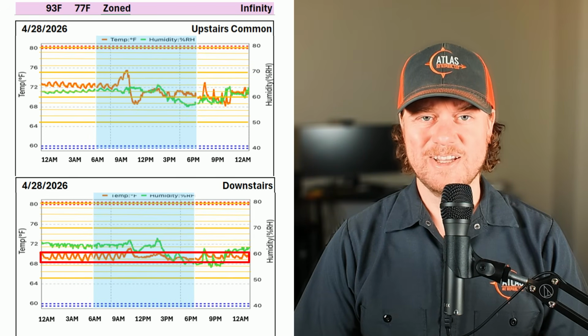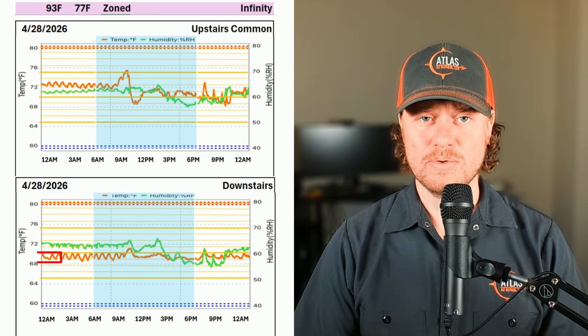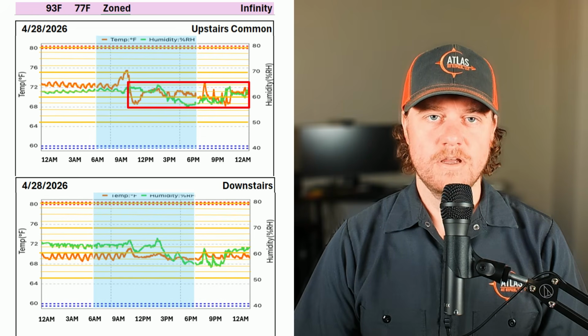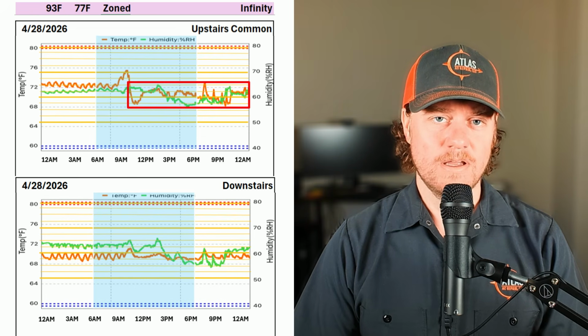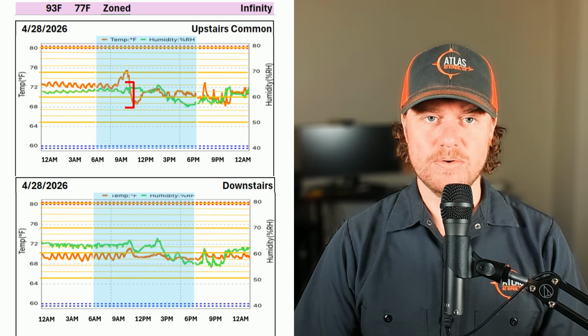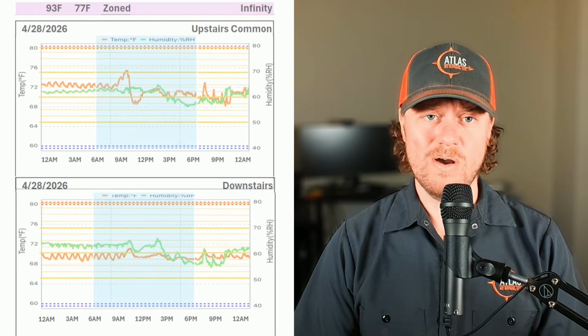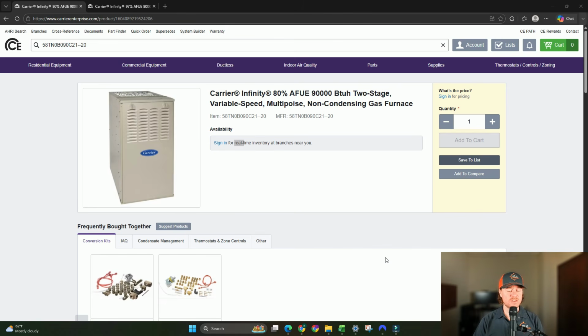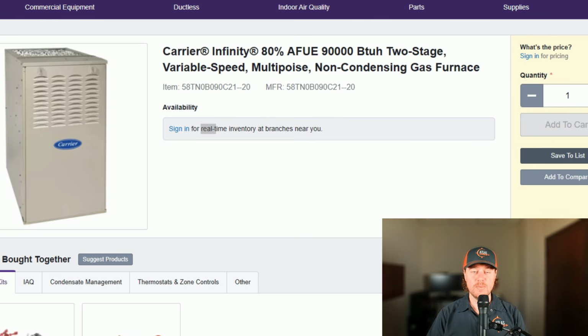In order to maintain a high level of comfort in every single zone, it's going to end up pushing itself. And where most people get airflow design wrong is they will size each zone for cooling mode. However, heating mode has different requirements. The easiest way to explain this is to use a gas furnace for an example. The most common furnace used with an Infinity system is a 58TN series furnace.